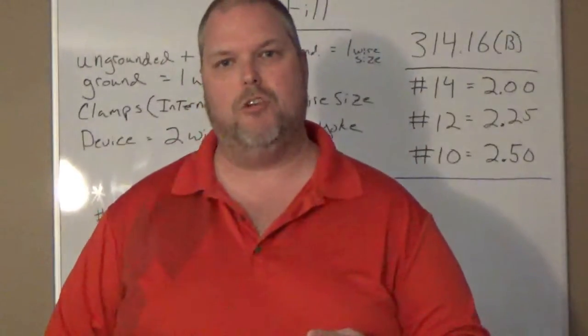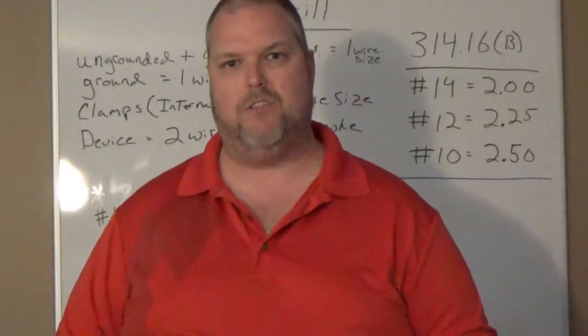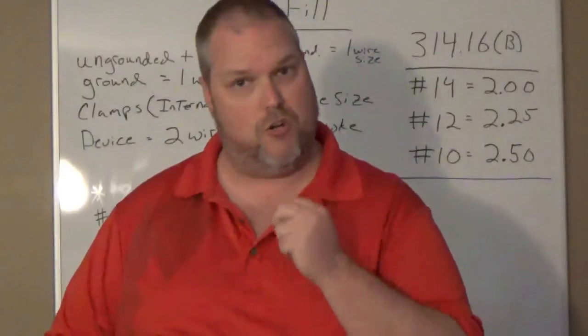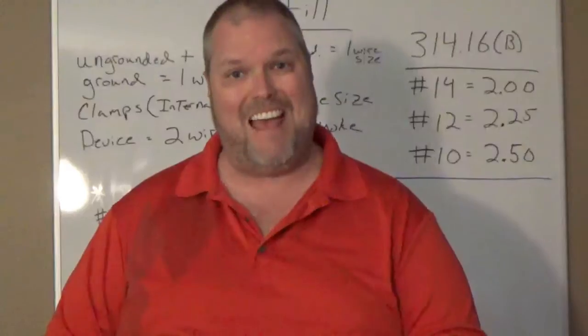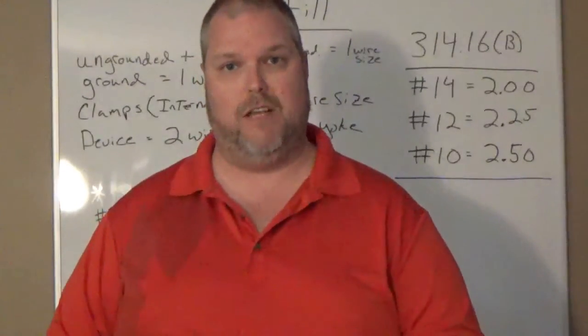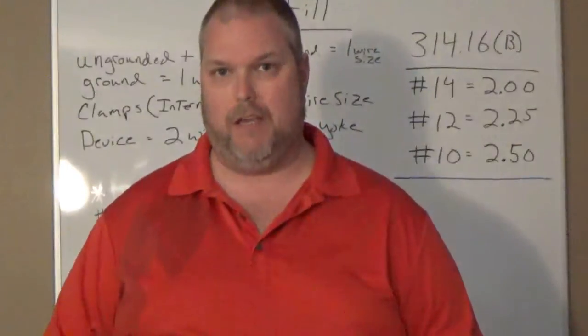And then our device, you get it. It's counted as two. So we actually have 10 conductors that we're going to size. So how do we figure this out? What we're going to do is we're going to take two, which is our two cubic inch volume per conductor. We have 10 conductors. We're going to take that 10, multiply it by two, and that's going to give us a volume of 20 cubic inches.